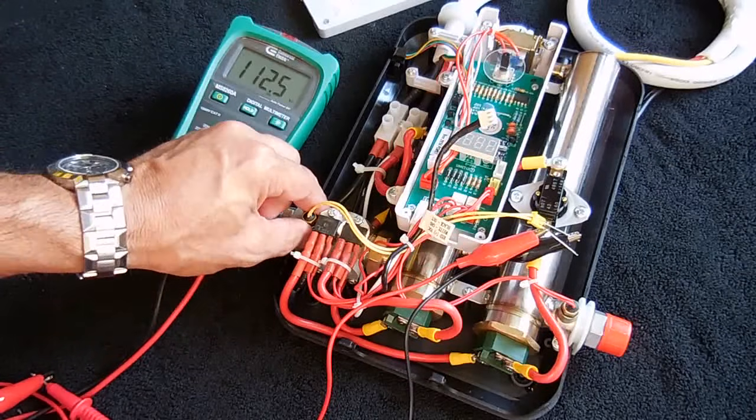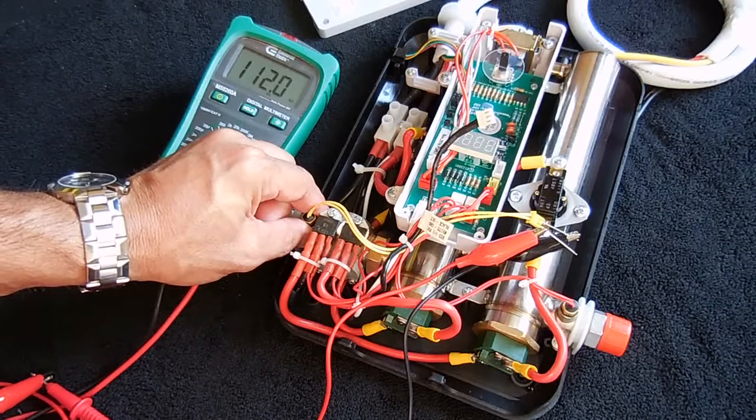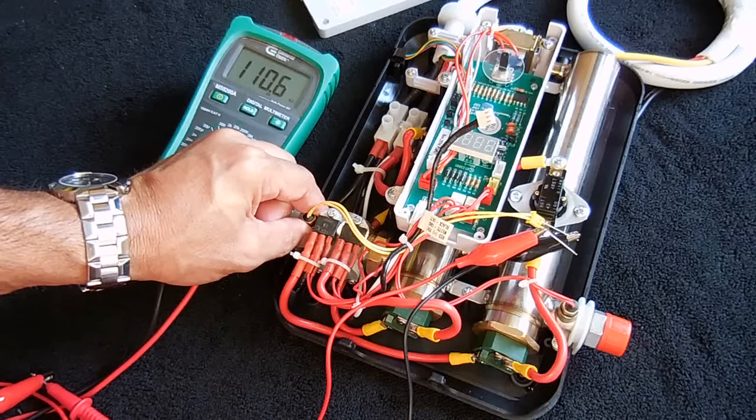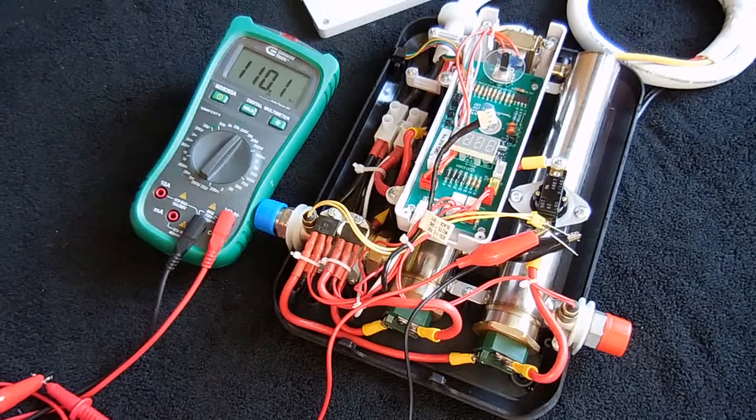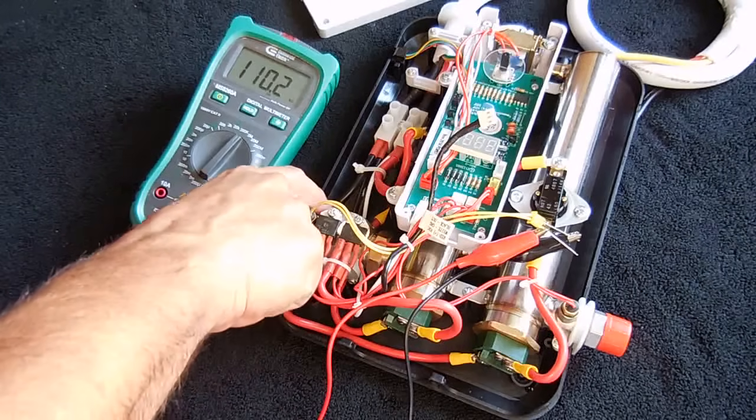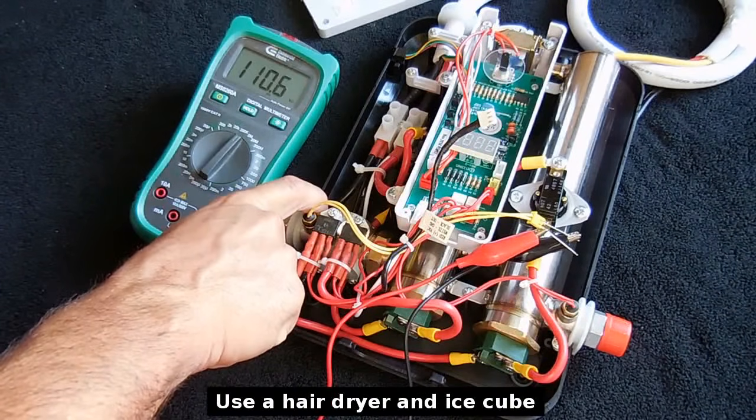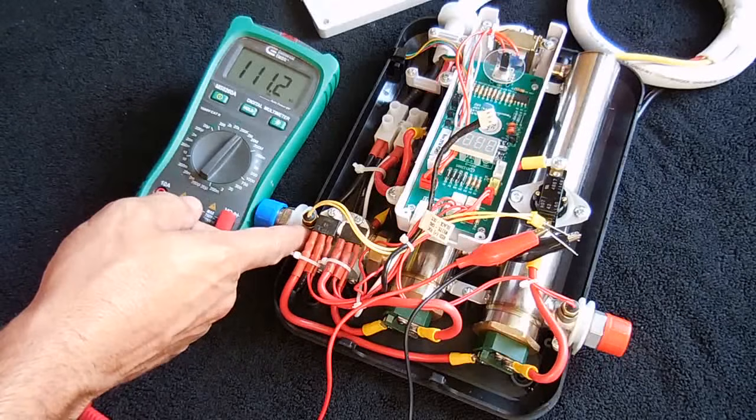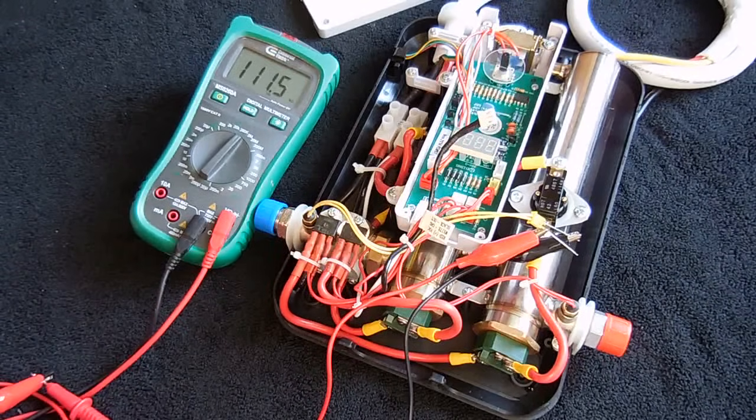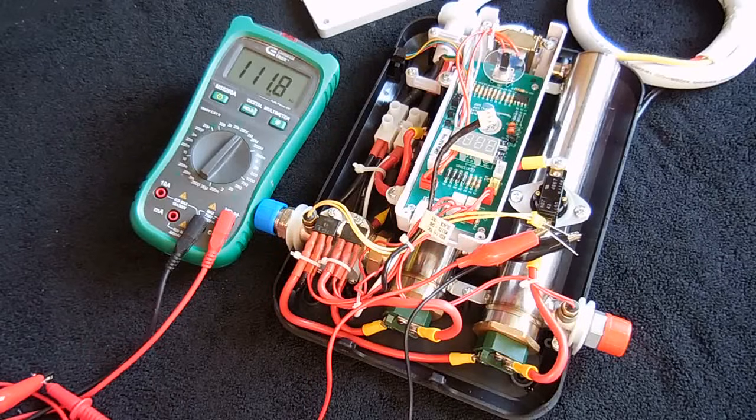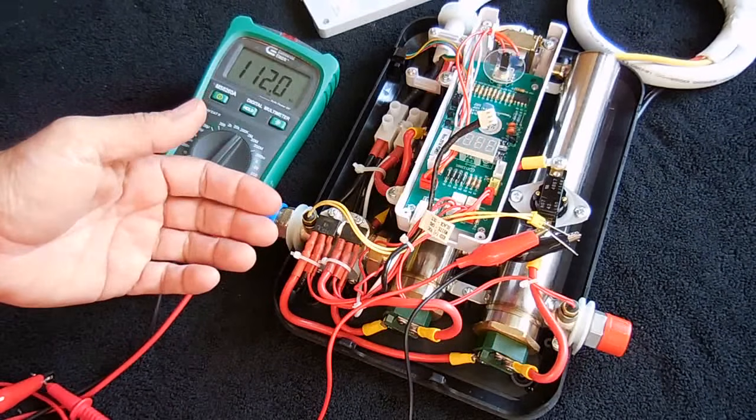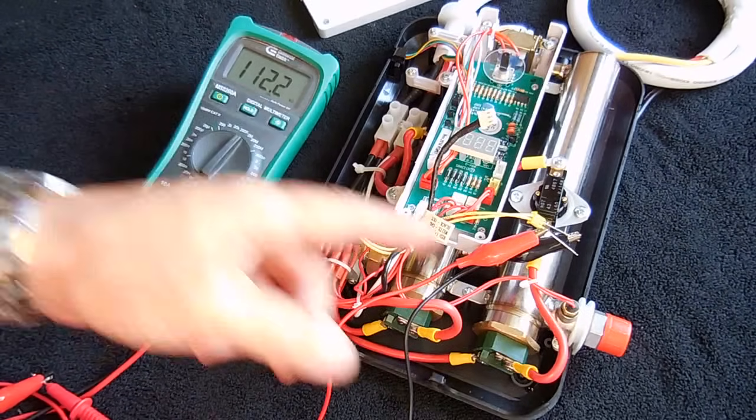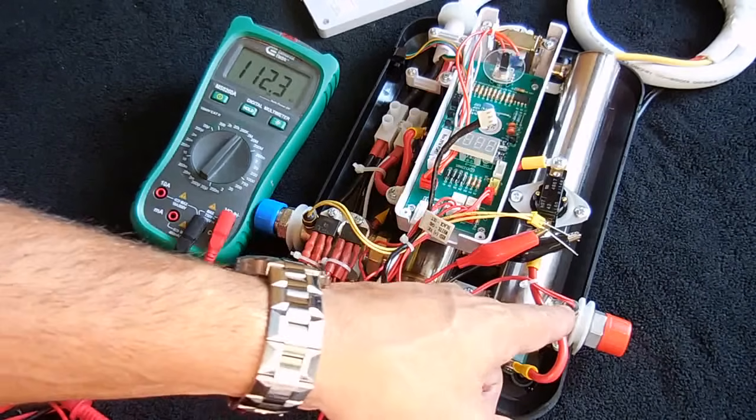Like that. As you can see, the reading is 112,000 ohms. If you apply heat like by holding my hand here, you see the value is dropping from my body heat. If you apply cold, I'm going to take some cold water, touch it to the side, and you can see the cool water is making it go back up. Put some cold water on there. And that's how you're going to test those. Test each one, make sure heat makes it go lower and make sure cold, by placing an ice cube, makes that number go much higher. Do the same test on the inlet and the outlet sensors.